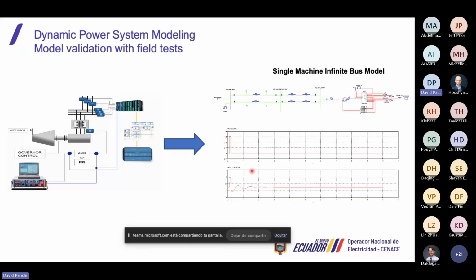Application of digital twin technology. The methodology developed must have a validated model that will allow obtaining a response similar to that of the real system, for which CENACE performs field tests that, together with the optimization algorithms that we have in the HyperSync software, allow us to obtain the real model of the generator system with our modeler in the simulator. So we do field tests with artifacts or automatic controllers. We register the test in the real plant, and with these test results, we build the model.